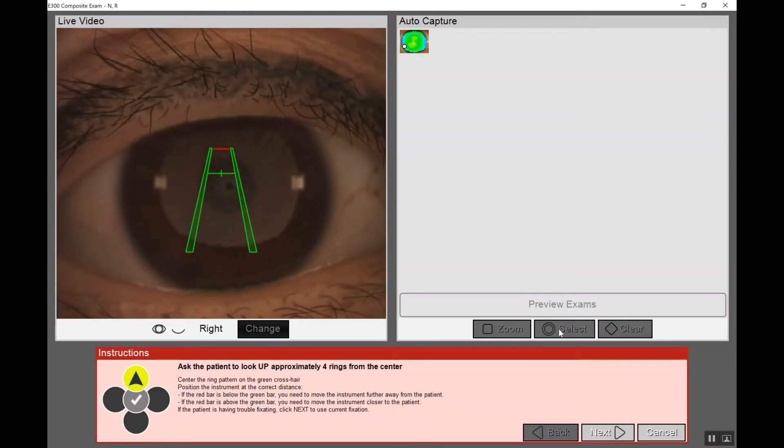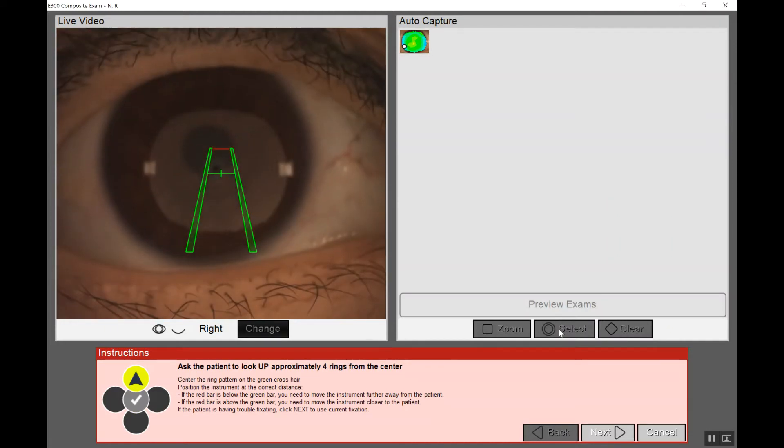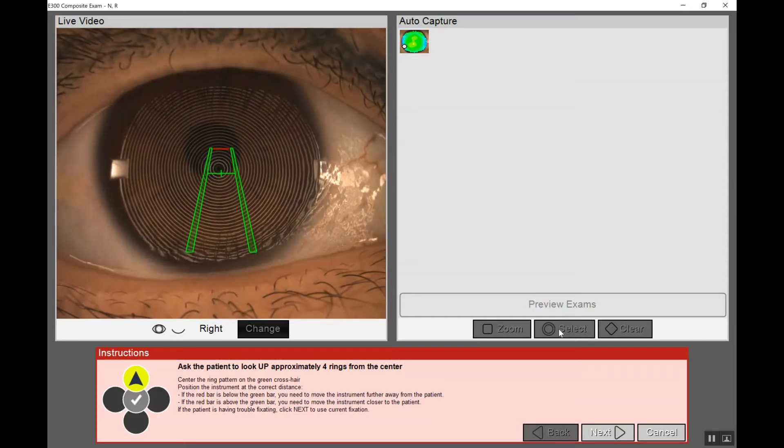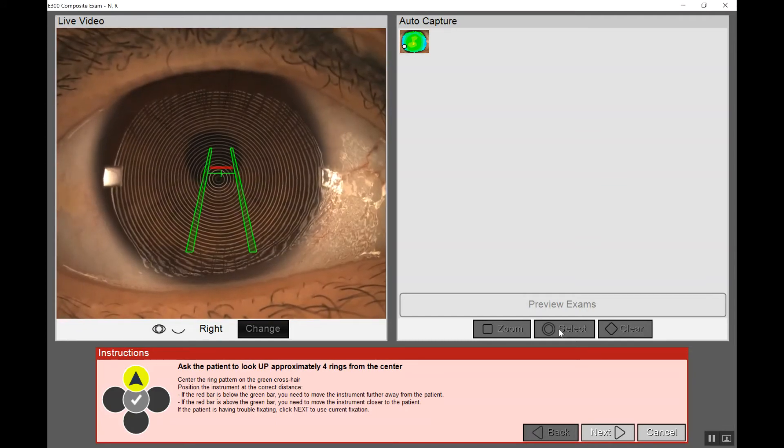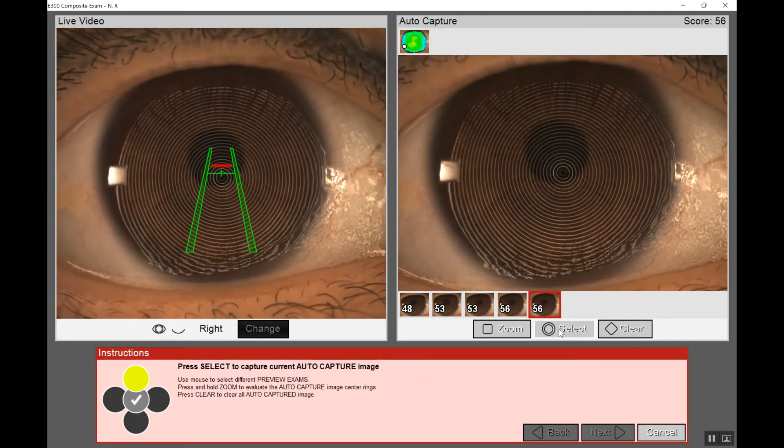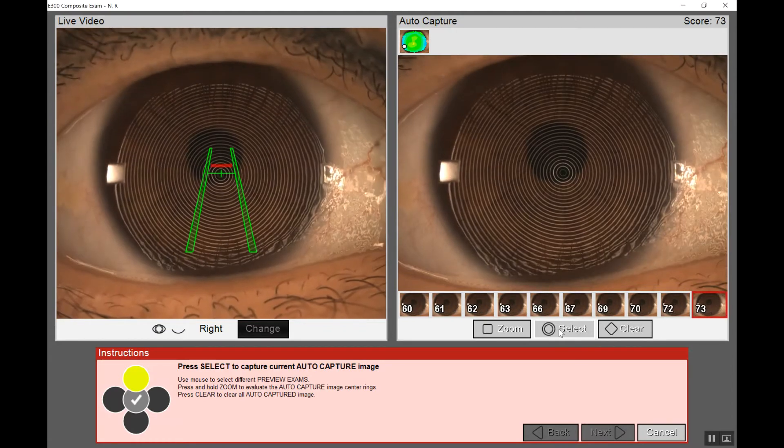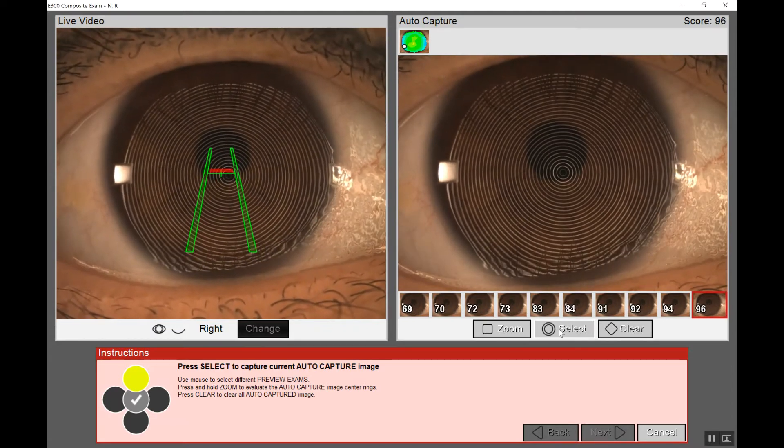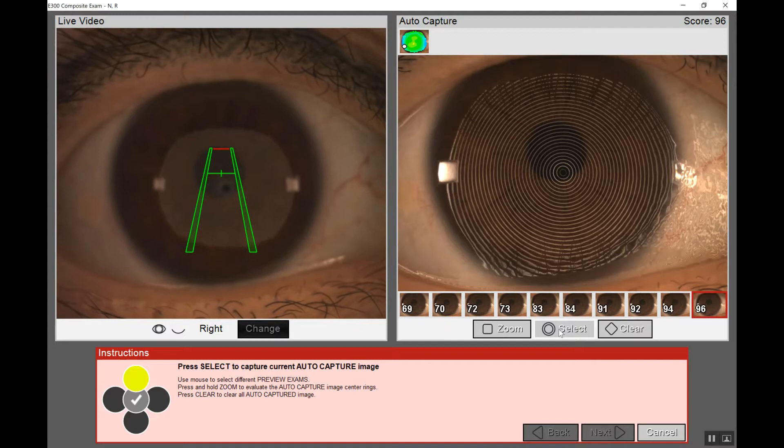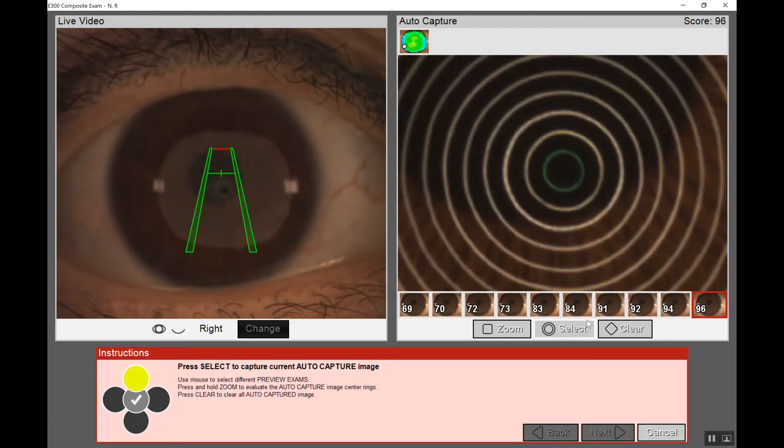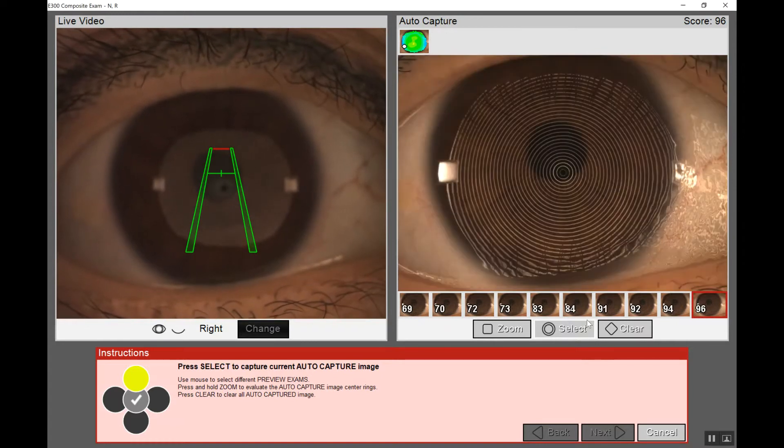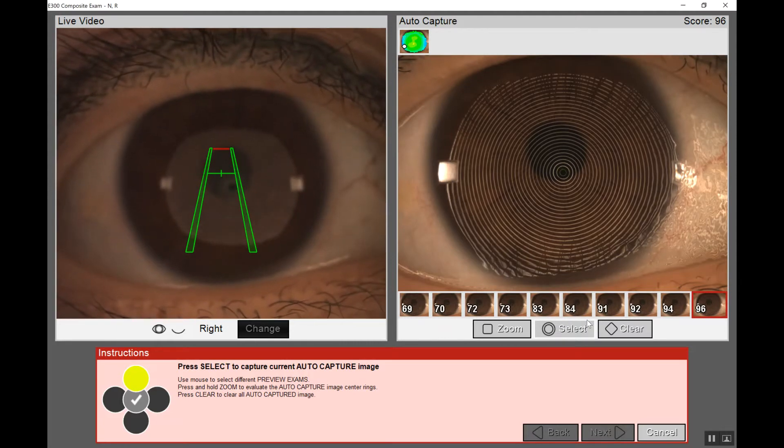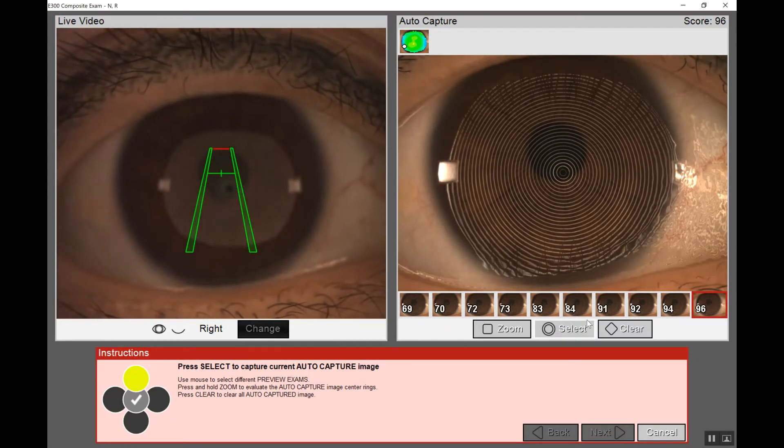Now the software is going to say ask the patient to look up approximately four rings. So your patient will count four rings from the center and fixate on that fourth ring up. If the lower lid is in the way you can ask the patient to pull down on their cheek. In this case we're able to stretch the rings down to the inferior cornea. We'll ask our patient to blink and then move in, steady over center and we have a 91, 92, 94, 96%. Again we can hold down the square key to make sure the rings look parallel and even, that we didn't have any tear film breakup. If we weren't happy with the images we can select the diamond to clear these images out and start again. But since we're happy let's click select.